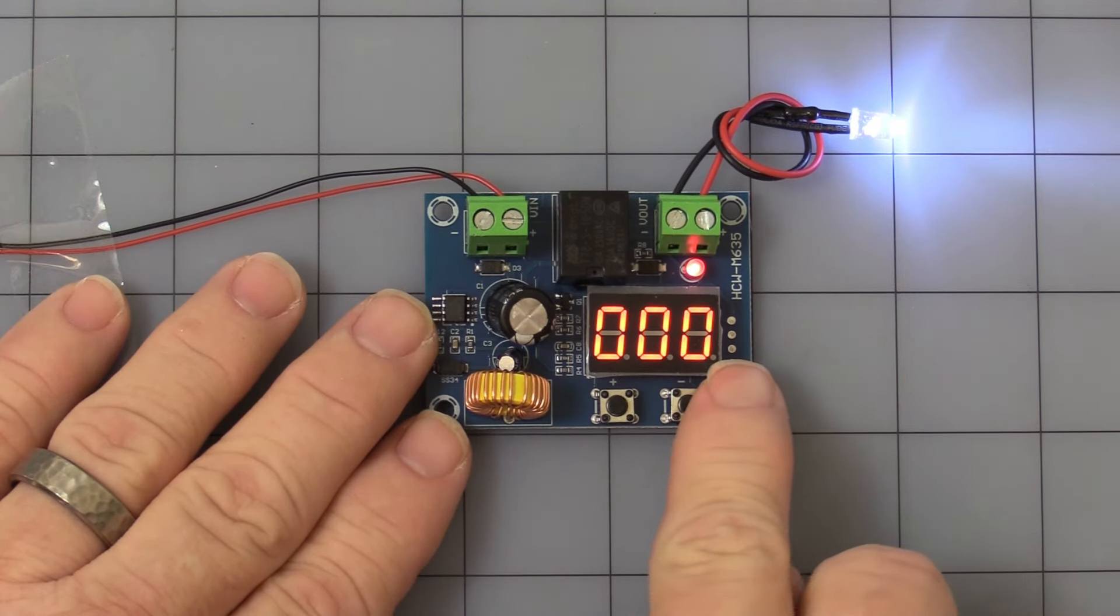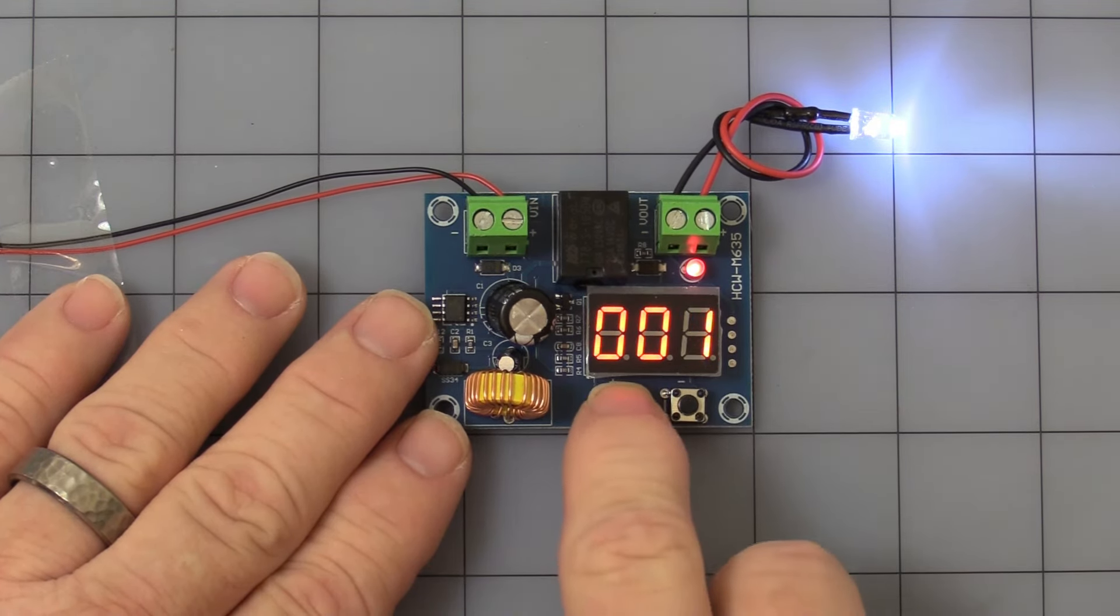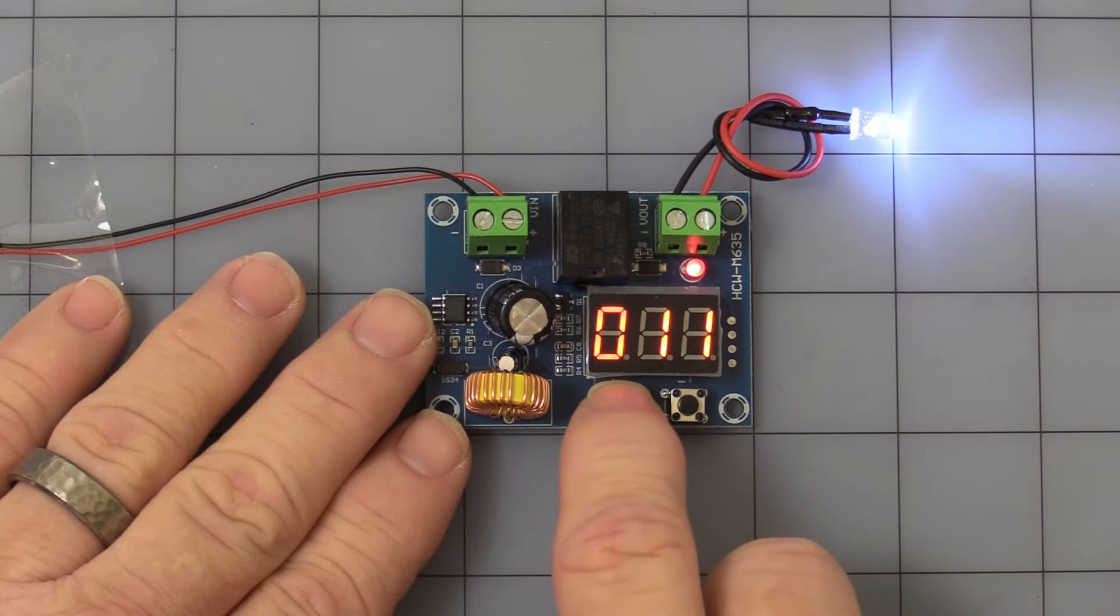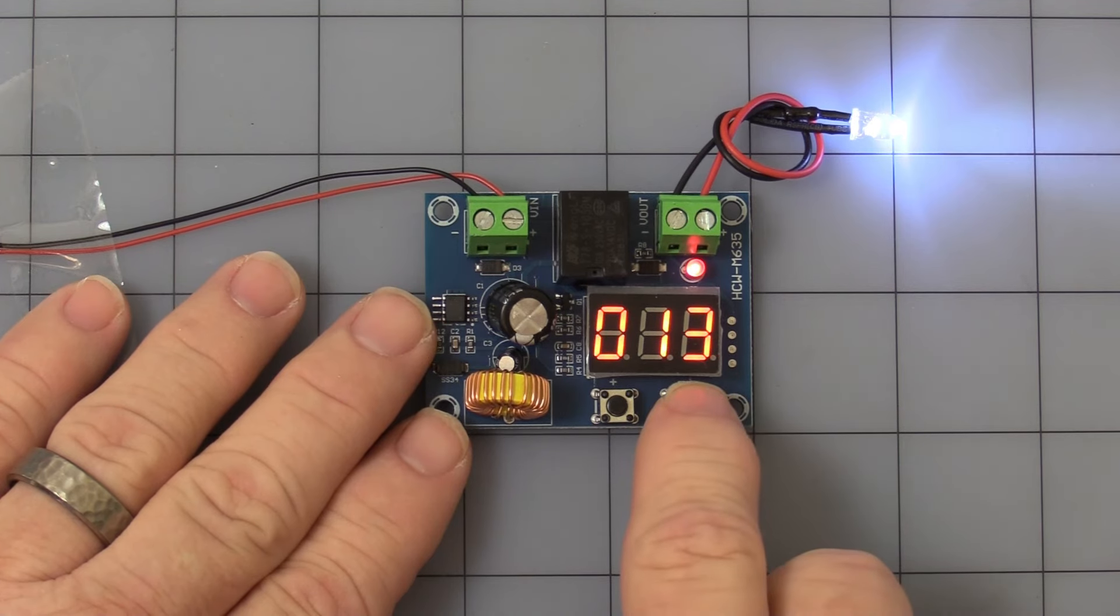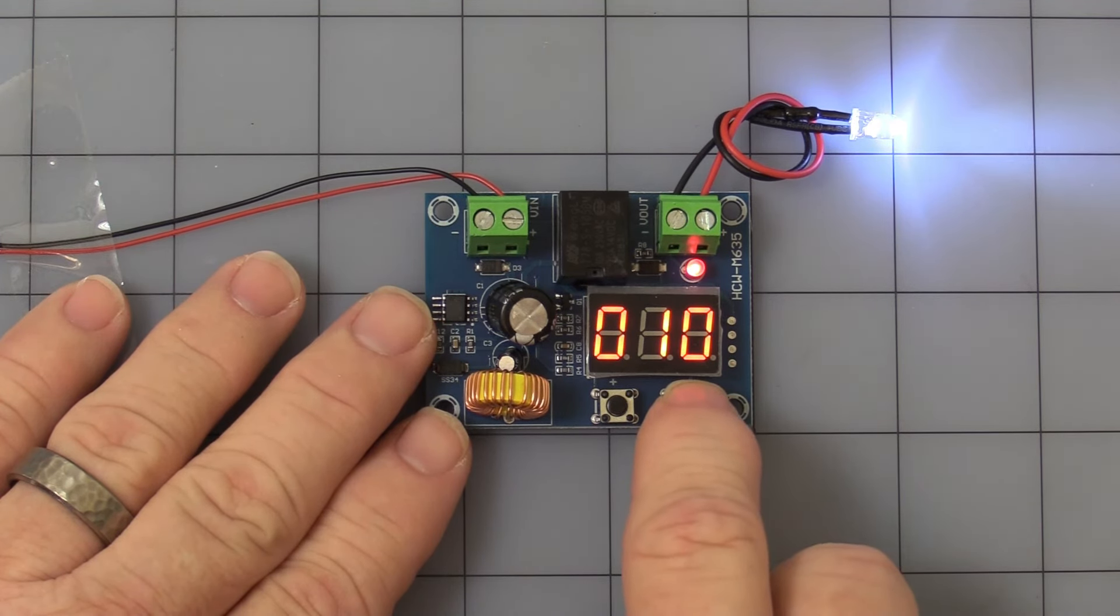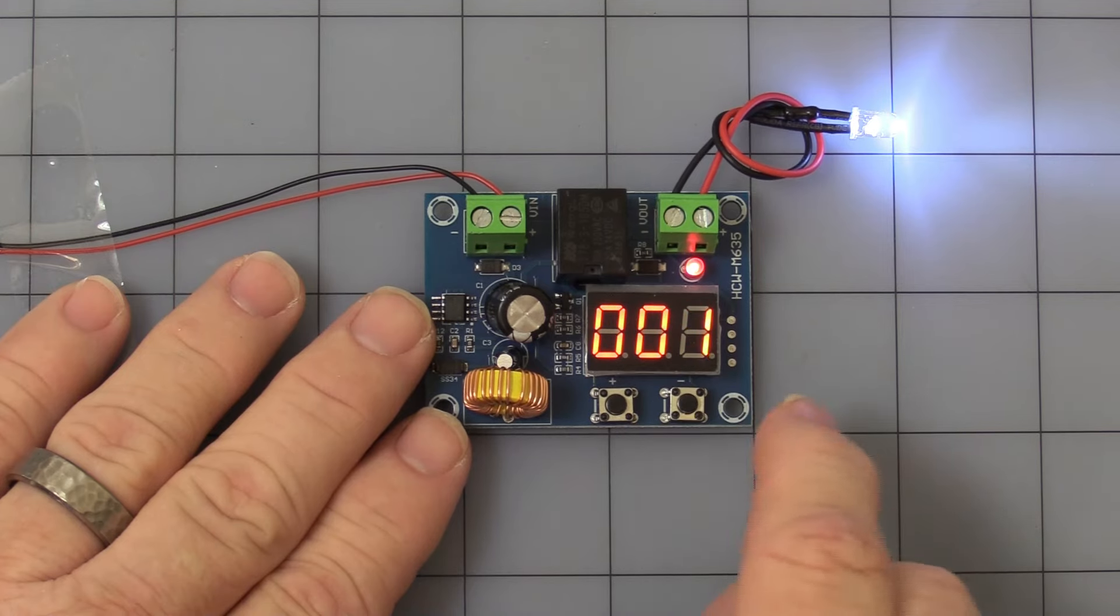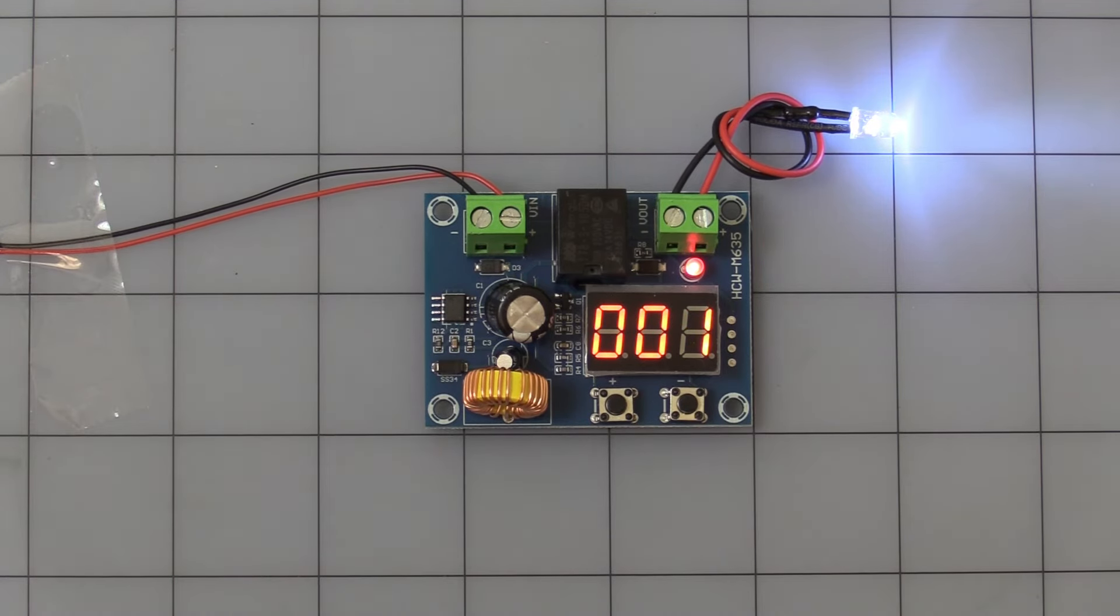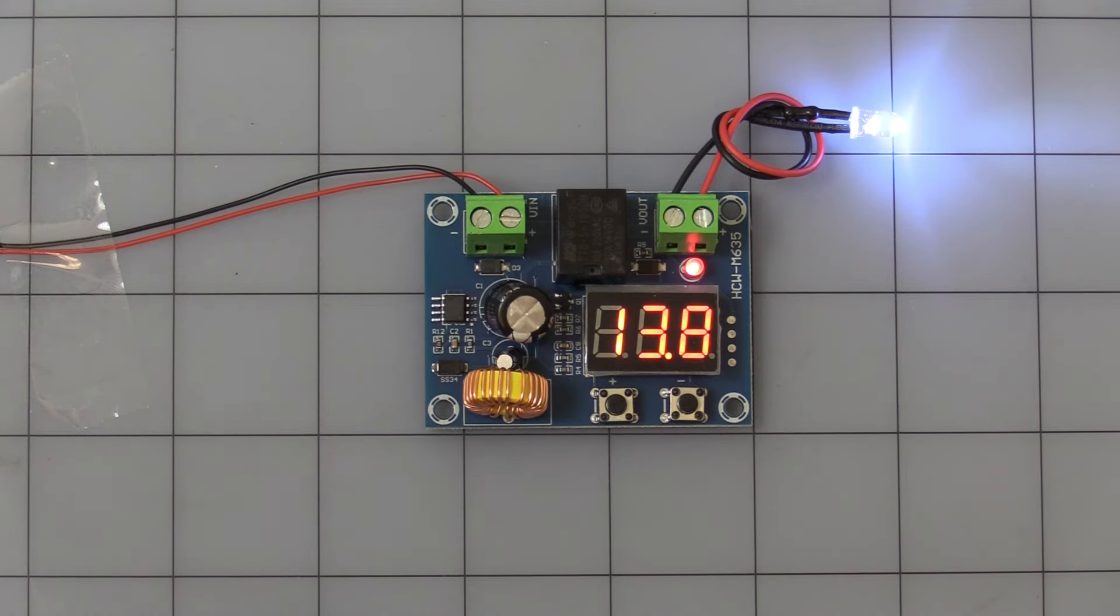Okay, when you see that little IN flashing there, this is your delay time. It says 10 minutes, but I've run it up to 60 minutes and tried it. It does work. So let's just, for sake of the video, stick to one minute. All right, this is a one minute delay from when it shuts down, one minute from the time when it goes back up to acceptable voltage.